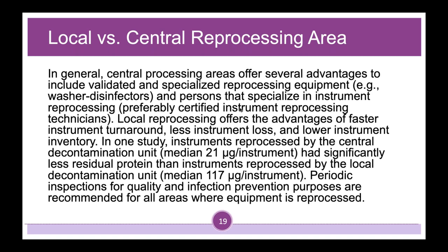Local versus central reprocessing area. In general, central processing areas offer several advantages, including validated reprocessing equipment such as washer disinfectors, and persons who specialize in instrument reprocessing, preferably certified instrument reprocessing technicians. Local reprocessing offers faster instrument turnaround, less instrument loss, and lower instrument inventory. In one study, instruments reprocessed by the central decontamination unit had significantly less residual protein than those reprocessed by the local decontamination unit. Periodic inspections for quality and infection prevention purposes are recommended for all areas where equipment is reprocessed.